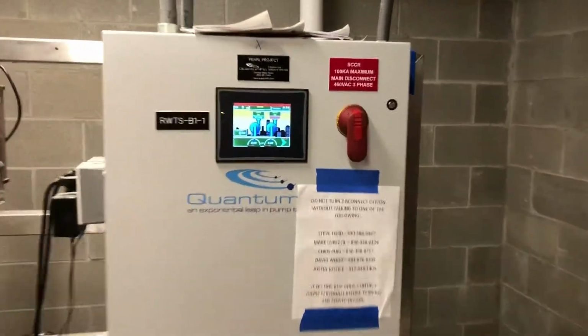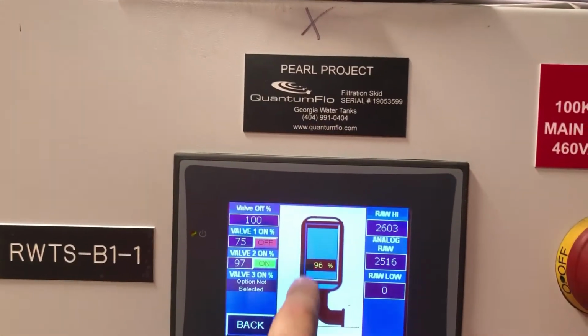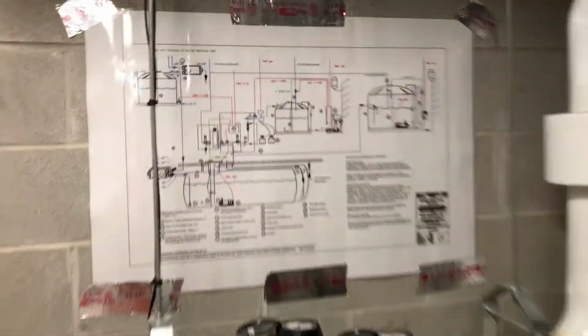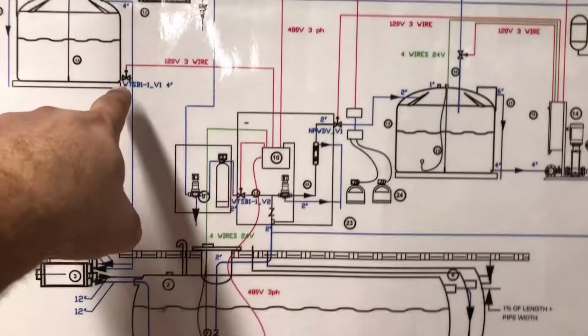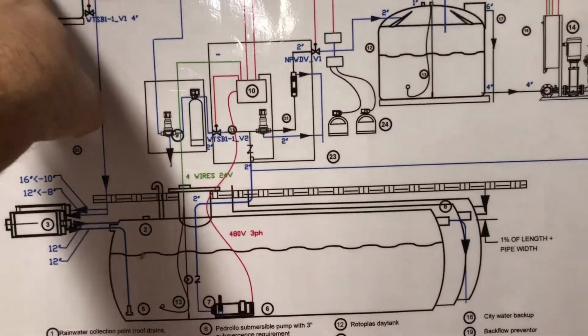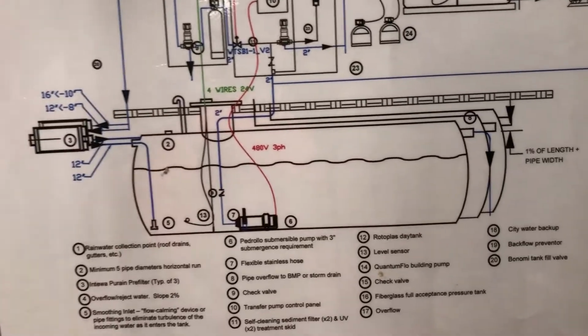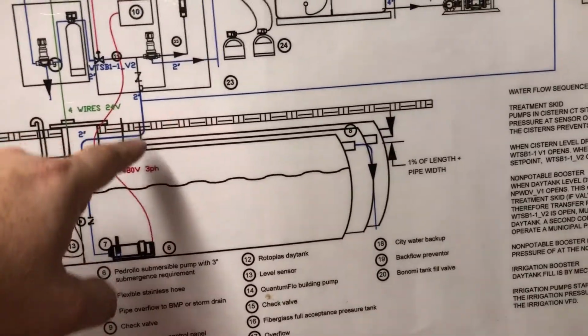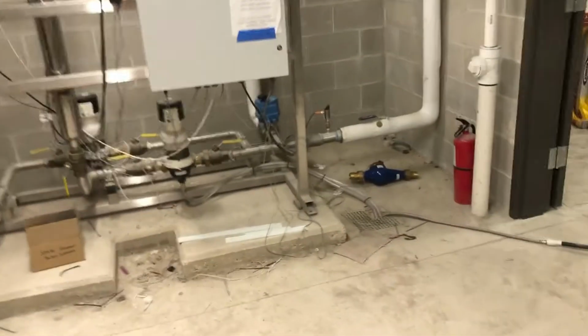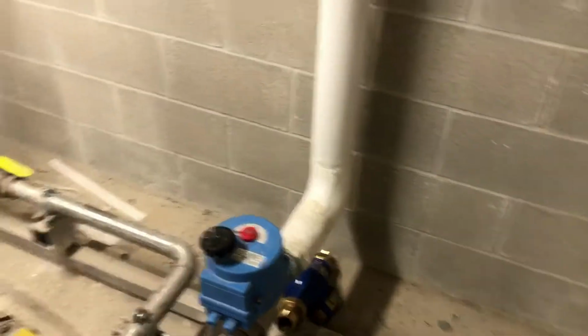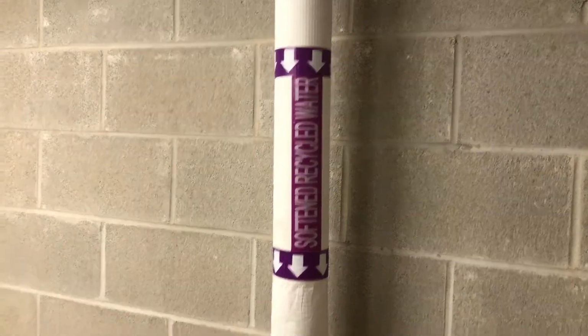This level is monitored on the treatment skid over here. If you go to tank, this shows you the level of that cistern. And these valve 1, valve 2 control how we bring water in there and how we use the reuse water. Valve 1 is this one here. When there's available space in the cistern for more rainwater, this valve opens and this stored rainwater flows by gravity down here. When this level gets too low, then we actuate this valve here, which allows reuse water from the city to flow through our treatment and to the day tanks.